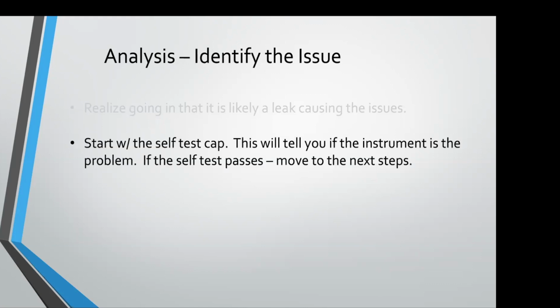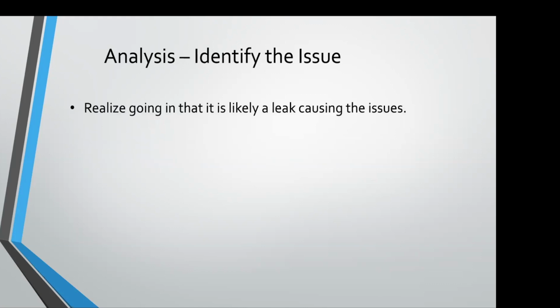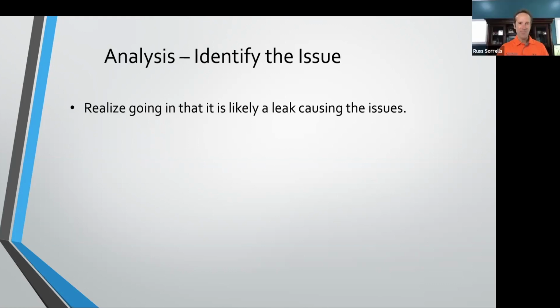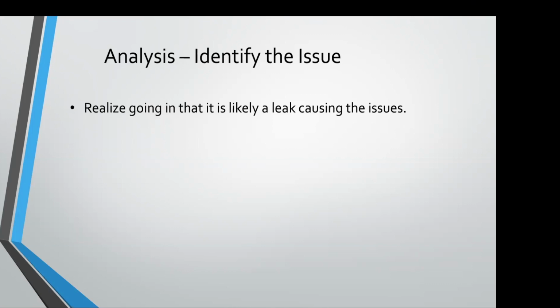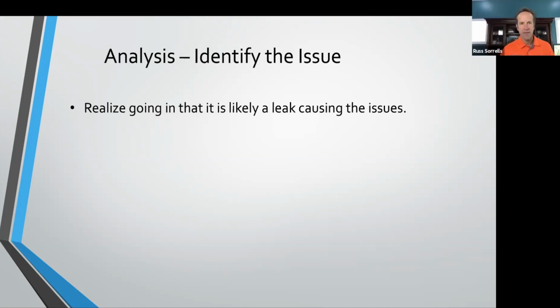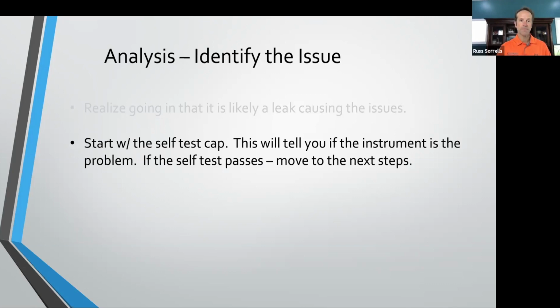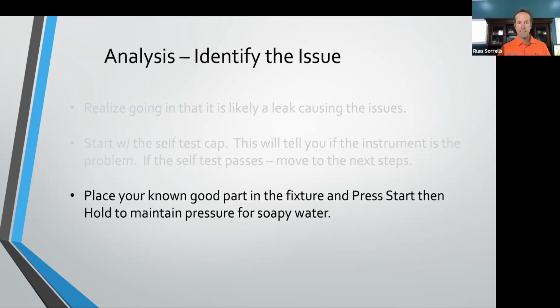Yep, and just for everyone, everything leaks, and leaks are not repeatable. So yes, that's right. And when we do our leak test training, we talk about that tortuous path, right? It's not a smooth path. That tortuous path is one of the main reasons why it's not repeatable. So we talked about starting with the self-test cap, plugging that onto the bottom of the instrument. And if the self-test passes, then we move on to the next step.